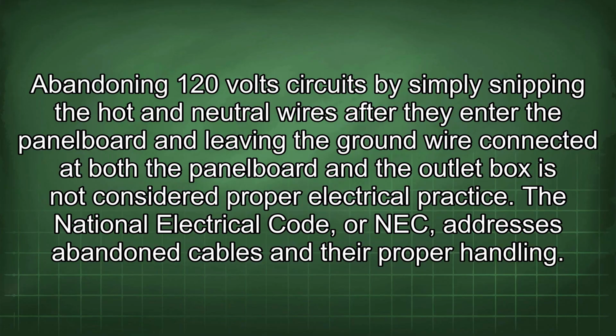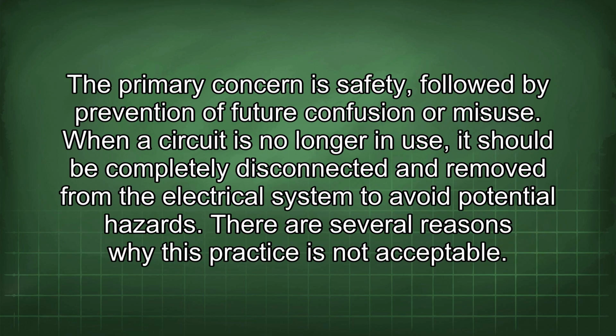Abandoning 120-volt circuits by simply snipping the hot and neutral wires after they enter the panel board and leaving the ground wire connected at both the panelboard and the outlet box is not considered proper electrical practice. The National Electrical Code, or NEC, addresses abandoned cables and their proper handling. The primary concern is safety, followed by prevention of future confusion or misuse.